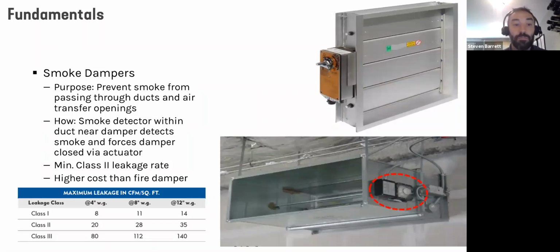These are required to be minimum class 2 leakage rate, which I've provided here in the chart. That's 20 CFM per square foot at up to 4 inches water gauge. And then beyond that, you can see in the chart, there's higher requirements for the higher static pressures. These are higher costs than fire dampers. They're more complicated because they require actuators, they require smoke detectors. So they're a little bit more complex.